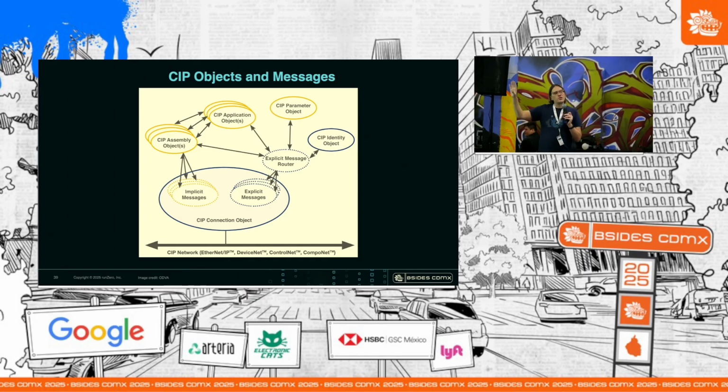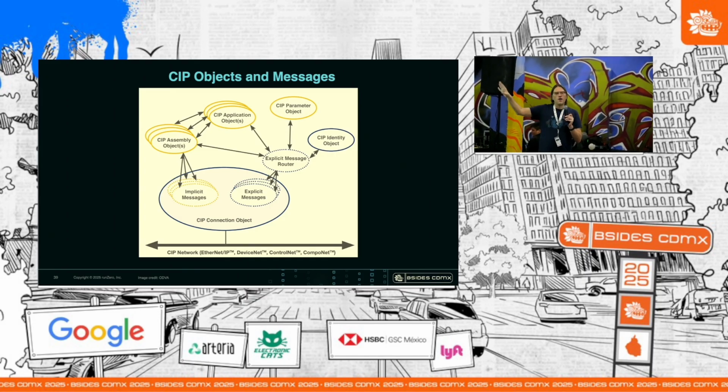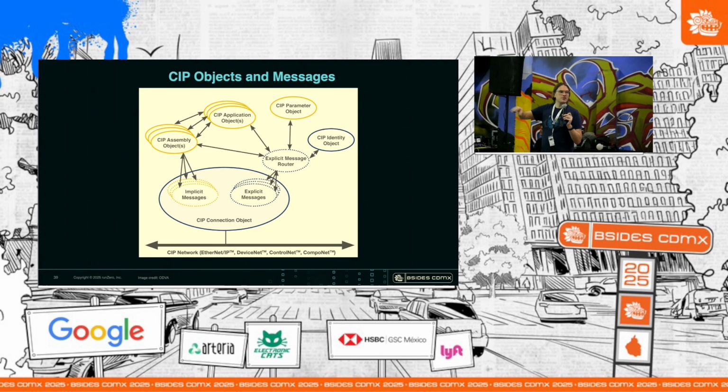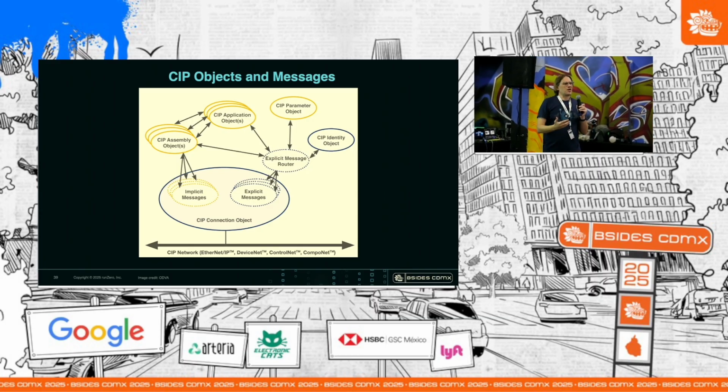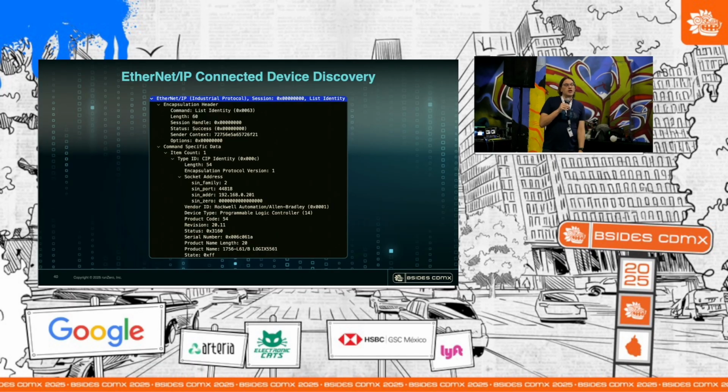And then again, once you've gotten into CIP space, all that's well defined. Every class of object has its own unique identifier that's defined in the standard, and every instance is just defined by number. Some of the classes can only ever have one instance, which is kind of silly, but what are you going to do? But you get there via one of those adaptations. For example, Ethernet IP is much lower level. You could almost imagine CIP as the Modbus encapsulated interface, and Ethernet IP as the sort of outer Modbus, right?